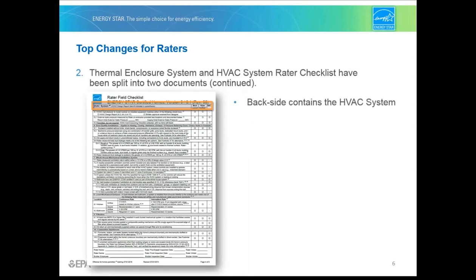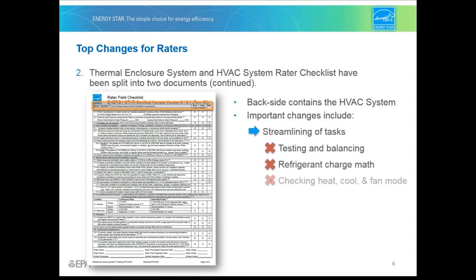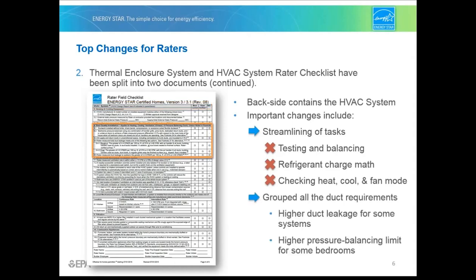The back of the rater field checklist contains the requirements for the HVAC system and includes some important changes. We streamlined the rater tasks, and items related to testing and balancing, refrigerant charge math, and checking the heating, cooling, and fan mode have been removed, among others. We've combined all of the duct requirements into one section, provided higher duct leakage limits for systems serving small spaces and systems with three or more returns, and a pressure balancing limit of five pascals instead of three for bedrooms with a design airflow of greater than 150 CFM.